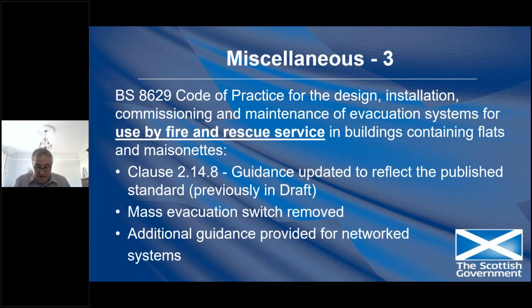In very large or very tall buildings, there may be a need for sub-panels connected to a data network using cables of enhanced fire resistance. Additional guidance is also provided on fault monitoring and location of cables in areas of low risk.